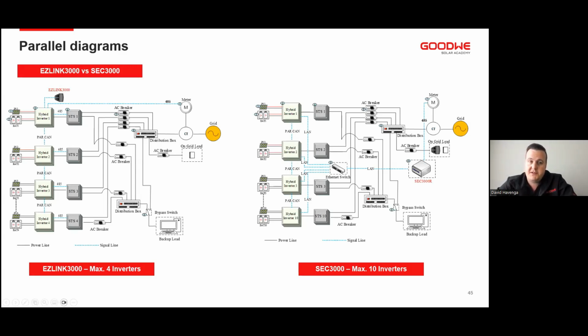with a communication cable. Then we will also launch later on in the year, or perhaps around Q1 next year, the parallel up to 10 inverters. We are still waiting for our SEC 3000, which hasn't been launched yet. It's still under development. But with the EZLINK and the 4 units, the changeover is seamless. So you have a seamless 10 millisecond changeover with 4 inverters in parallel. That means you can build up to a 200 kilowatt AC system for backup.